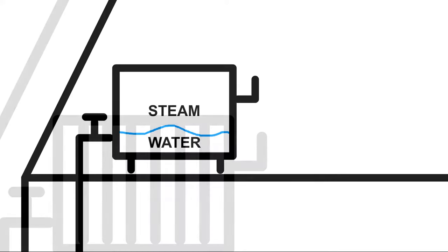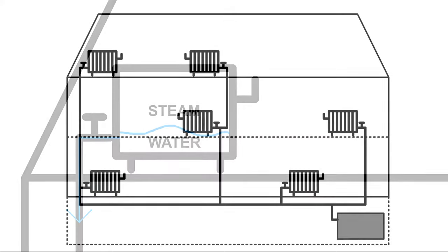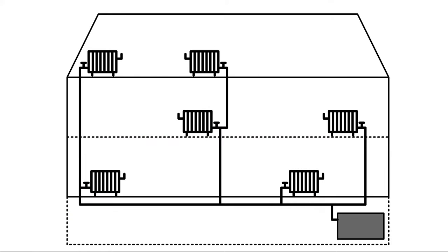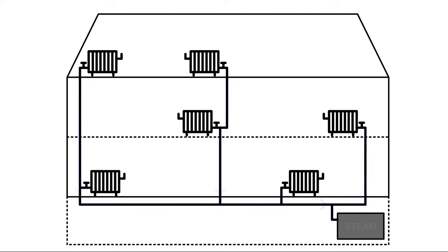closes the heat-activated valve. Simultaneously, as the steam condenses due to meeting a cold radiator, it will precipitate back as water and drain back the way it came from, making way for more steam to enter the radiator until it is hot, so you'll hear the vent hissing throughout the boiler's heating cycle. Once the boiler is off, all the steam condenses into water and drains back into the boiler. Nice. But if you're here, something's amiss in your steamy machine, so let's have a look at every issue I personally encountered and how I solved it.